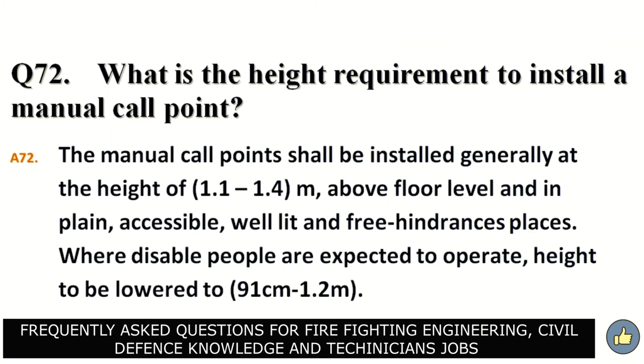What is the height requirement to install a manual call point? The manual call point shall be installed generally at the height of 1.1 to 1.4 meters above floor level and in plain, accessible, well lit and hindrance-free places. Where disabled people are expected to operate it, the height is to be lowered to 91 centimeters to 1.2 meters.